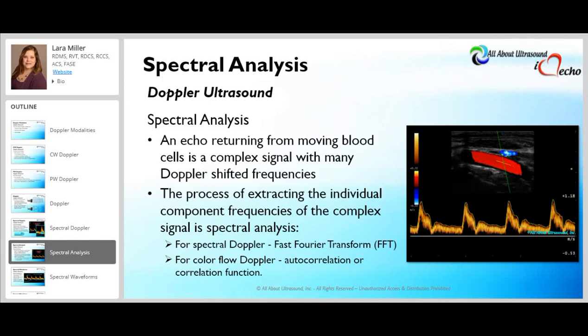In order to have a spectral or color display, the ultrasound system must perform spectral analysis. The echo returning from a moving blood cell is a complex signal with many Doppler-shifted frequencies, so spectral analysis extracts the individual component frequencies from that complex signal. For spectral Doppler, the system uses fast Fourier transform. For color flow Doppler, it uses autocorrelation.